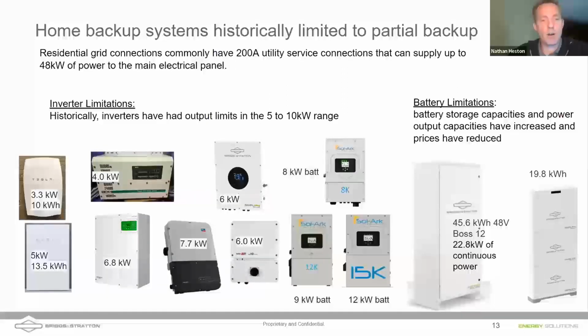We've got a Trace inverter there, the Schneider SCP, the Schneider, Daniel, help me out on that one. 6048, I believe it's 60. Yeah, I think it's the Context and maybe yes, a storage there as well. SolarEdge is here as well. Our 6 kilowatt Briggs inverter, all of these require critical loads panels, even the Sol-Ark 8K and the Sol-Ark 12K, right? The capacity is just not there to back up the whole home. The true advantage of the Sol-Ark 15K has to do with that 200 amps of pass through. We can pass 200 amps from the grid through the Sol-Ark 15K and back up the entire loads panel.